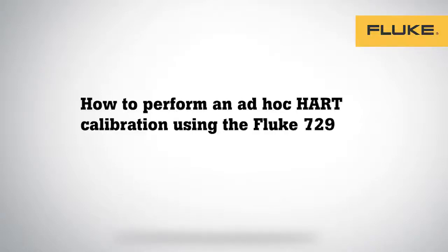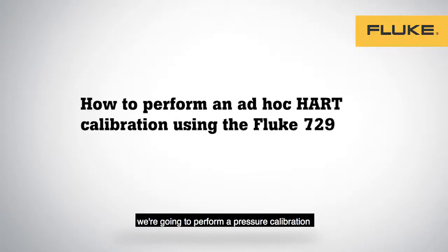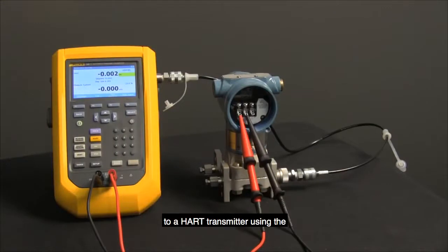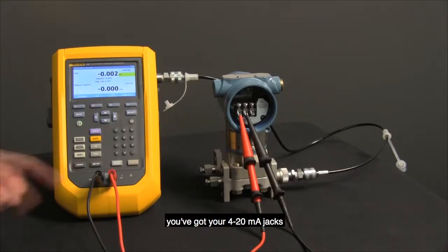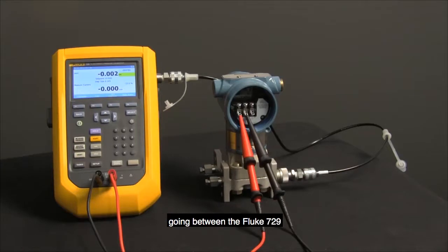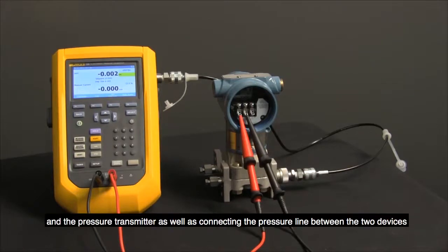In this video, we're going to perform a pressure calibration to a HART transmitter using the Fluke 729 automatic pressure calibrator. So to get things connected up, you've got your 4-20 milliamp jacks going between the Fluke 729 and the pressure transmitter, as well as connecting the pressure line between the two devices.